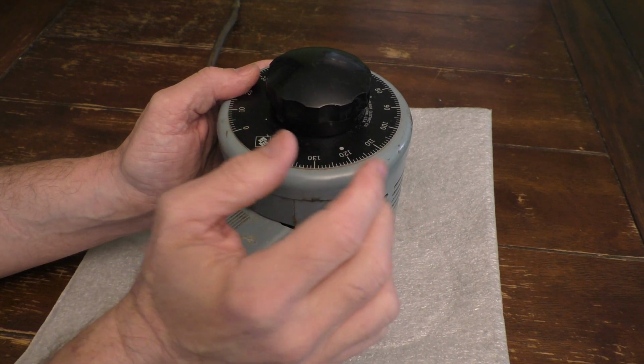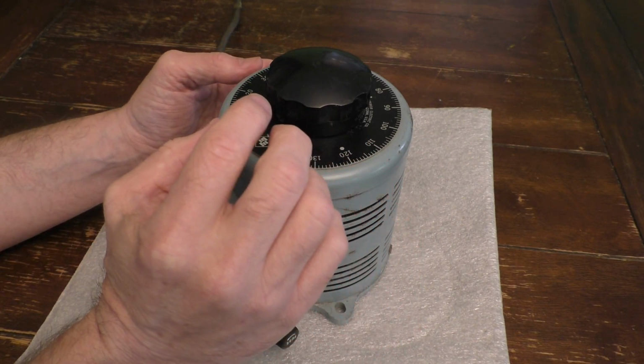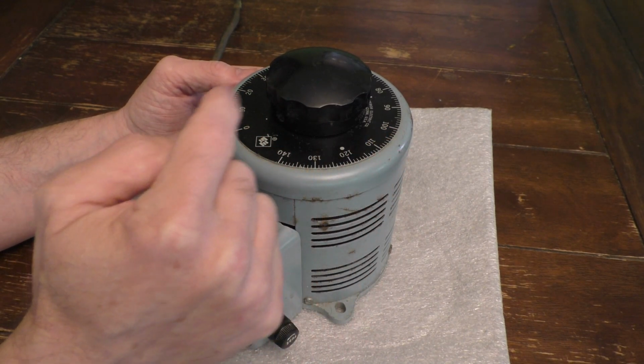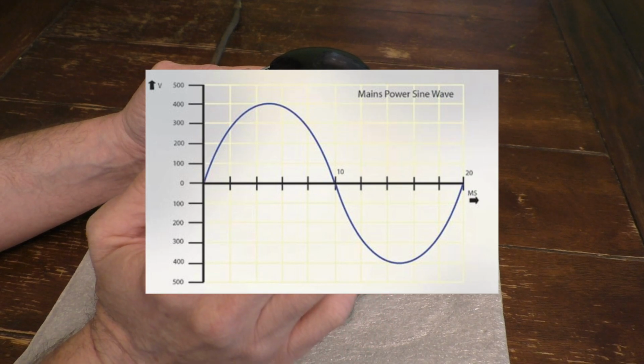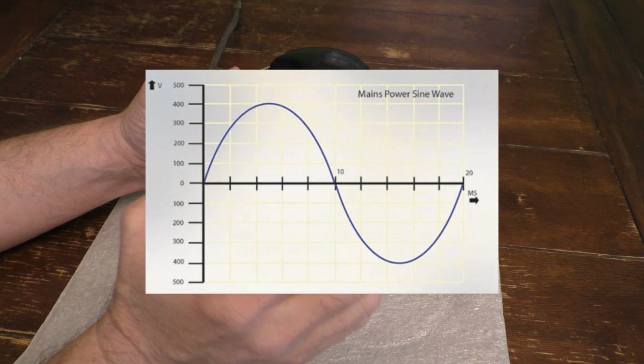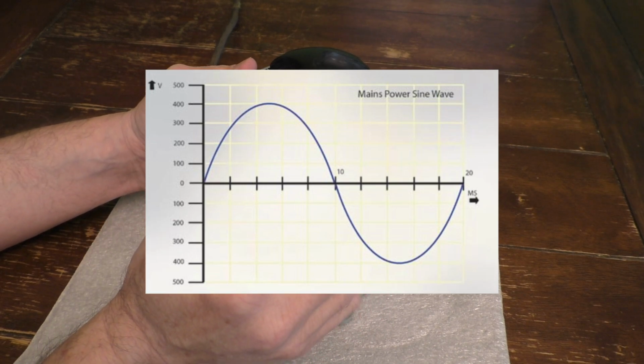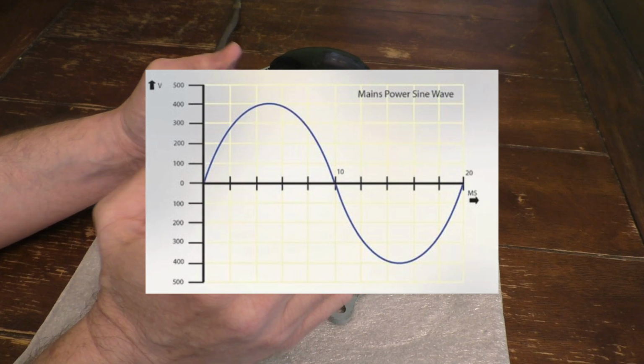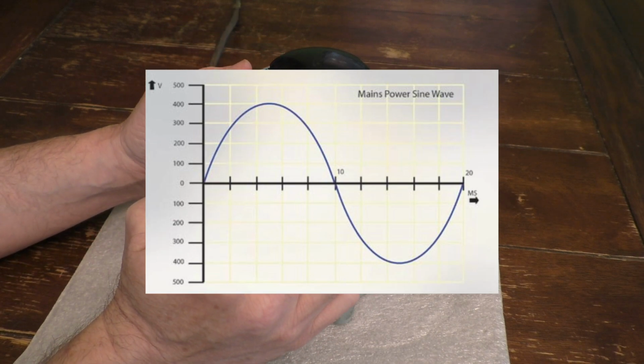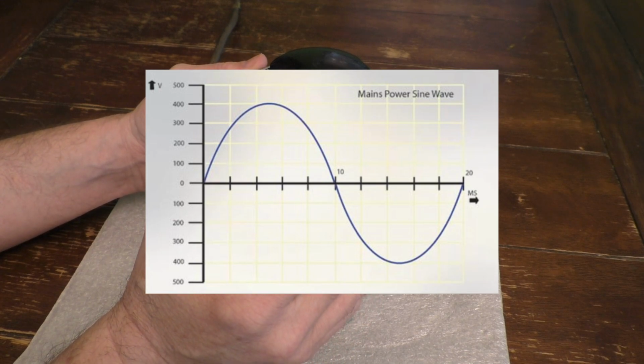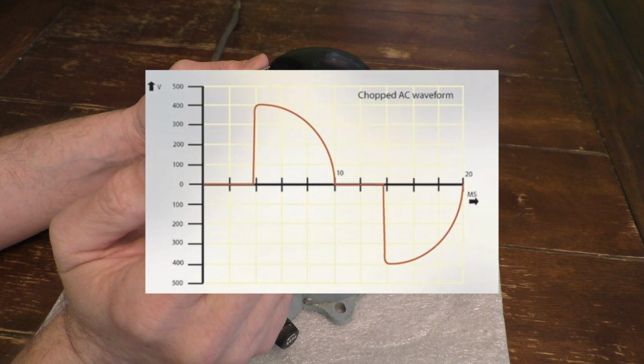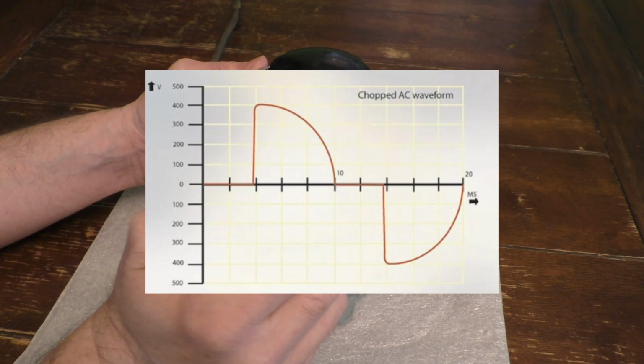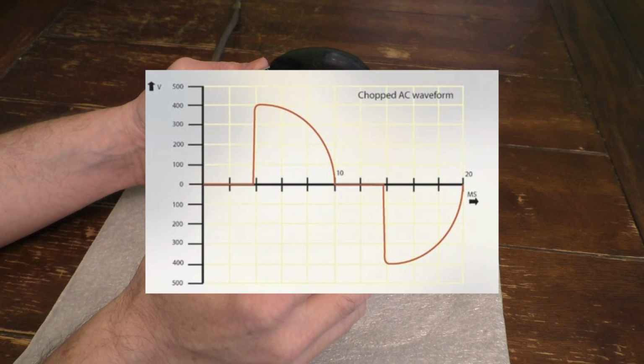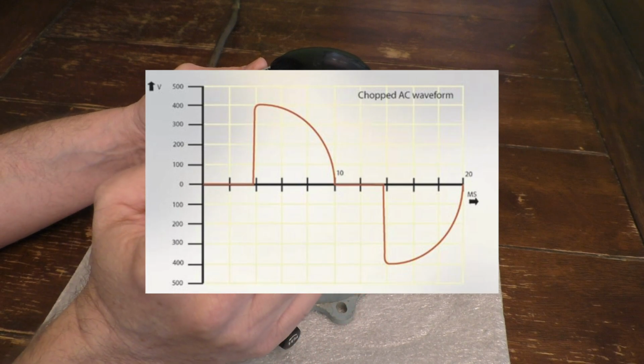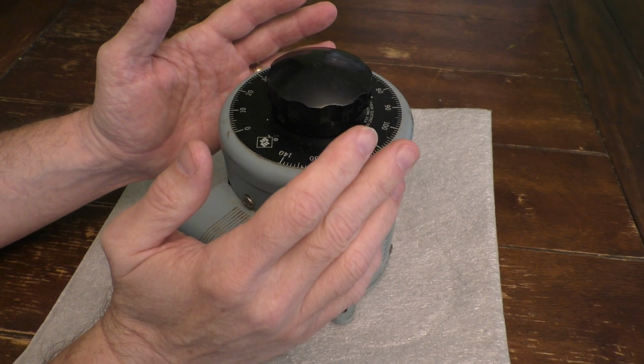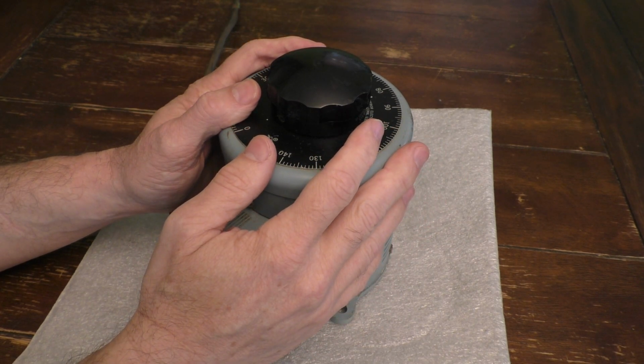Typically in your wall outlets you see dimmer switches. If you think about an AC sinusoidal wave, the autotransformer will reduce or increase the voltage, but you'll maintain that constant sine wave - you basically get a perfect sine wave still, even though you're modifying the voltage. A dimmer switch, on the other hand, actually cuts the wave on one or both sides of the sine wave, so you don't get a pure sine wave on the AC current. So if you want that pure sine wave, you definitely want to use an auto transformer.